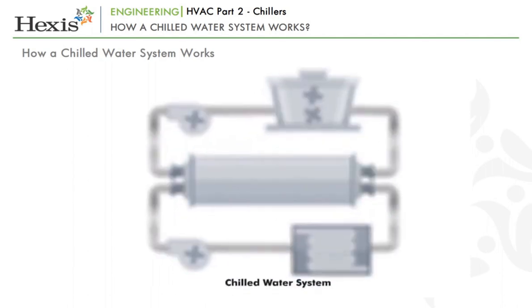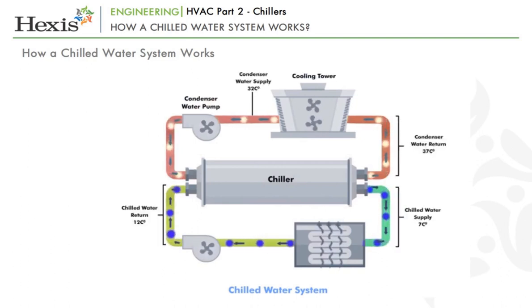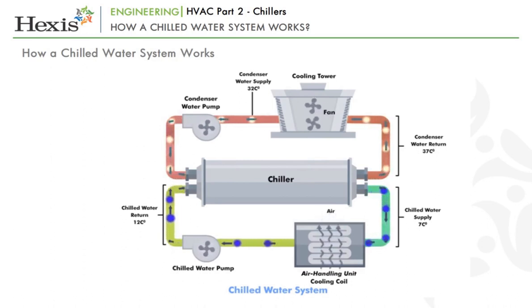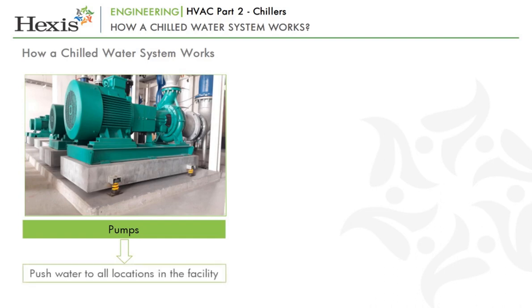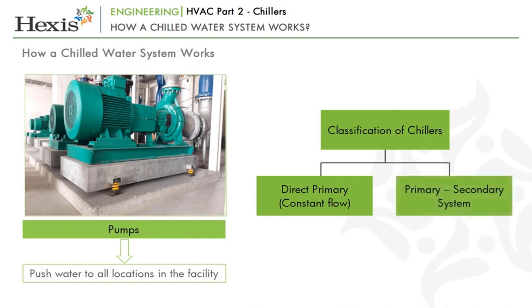Let's understand how a chilled water system works. The chiller basically removes heat from the water, which is used as a refrigerant to remove heat from the building. The chilled water circulates through a chilled water loop and through coils located in air handlers, absorbing heat from the building. It then returns to the chiller where the refrigeration process removes the heat from the water. The basic pumping arrangements used in chillers can be classified into two: direct primary, i.e. constant flow, and primary-secondary system. In a direct primary system, there is only one set of pumps used for distribution of the chilled water to the entire network and back, at constant flow irrespective of the load. This system is inefficient because of the wastage of energy, as the mixing of chilled bypass water with the return water reduces the efficiency of the chillers.